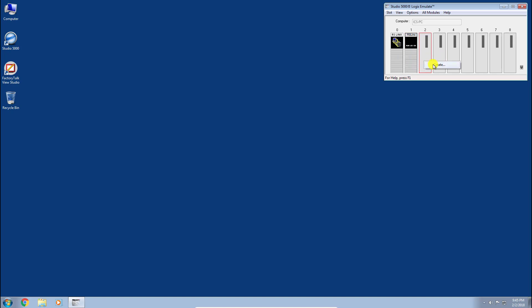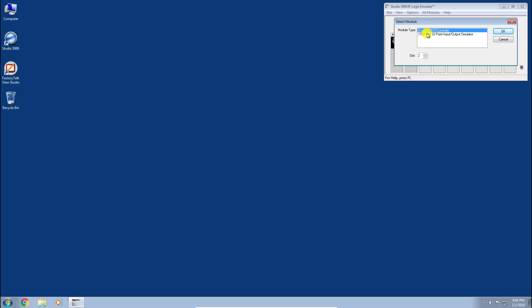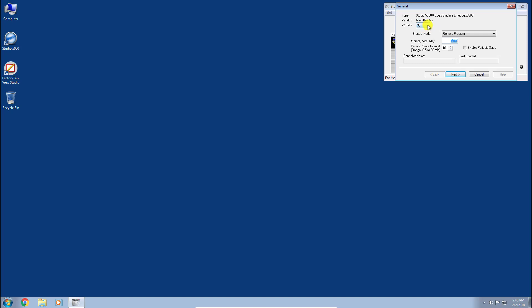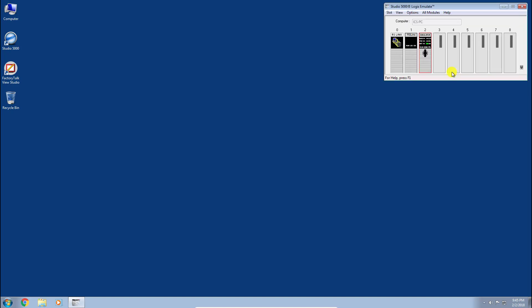I'm going to right-click on the first empty slot — slot 2 — to create our emulated processor. I'll select the Emulate 5570 controller, and you select the firmware version you want running in this controller. This should match the version of Studio 5000 software you're running. I'm running version 30, so I'll leave it at the default. I'll click through the defaults and finish — and there we go, our emulated processor is now running in slot 2.